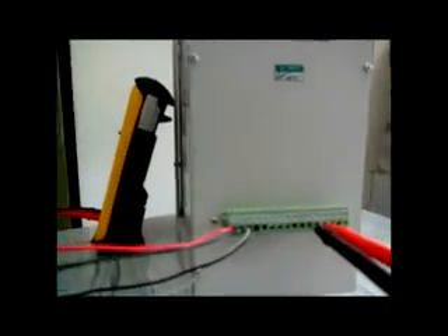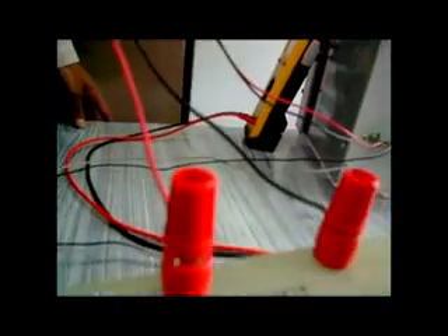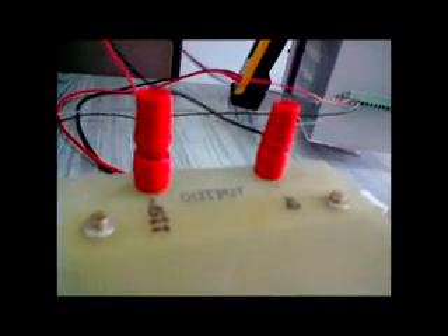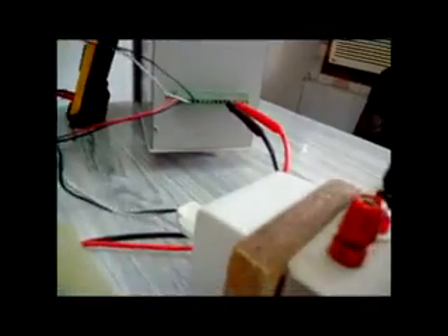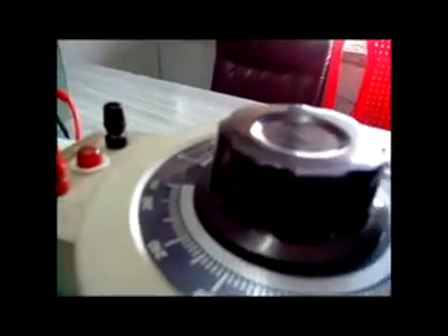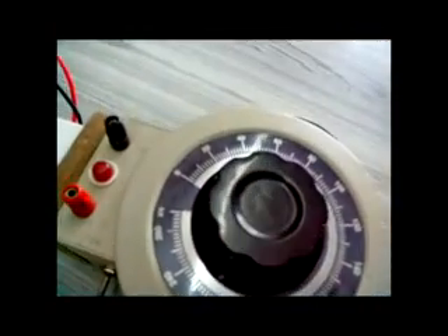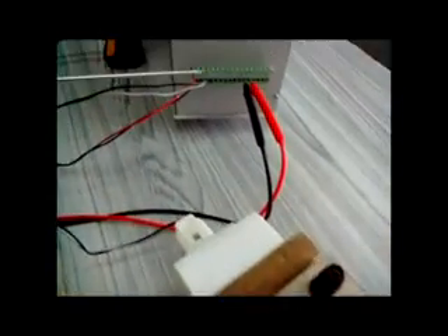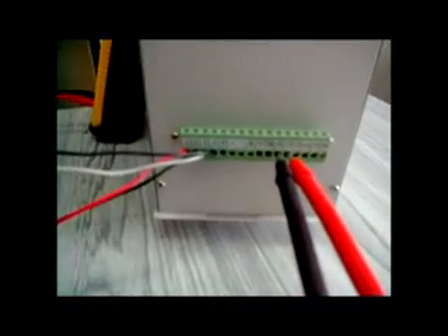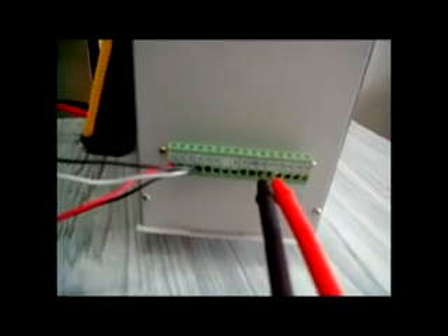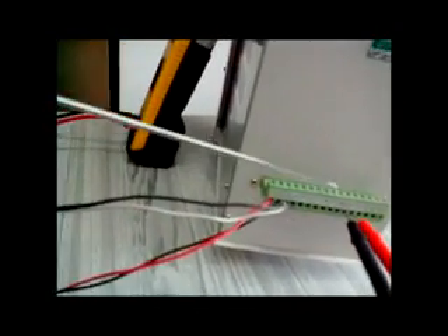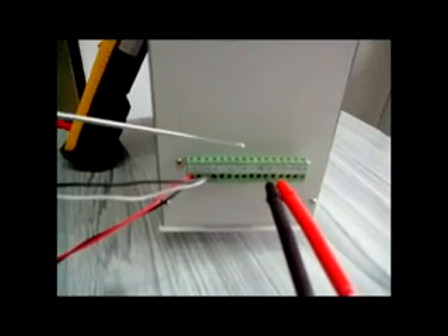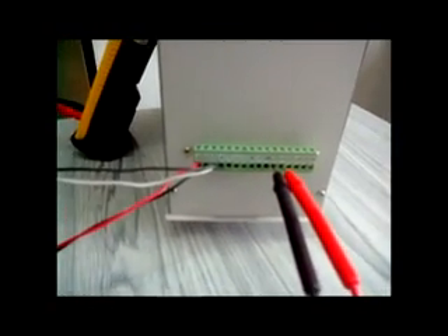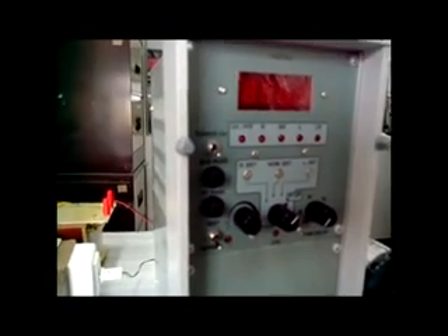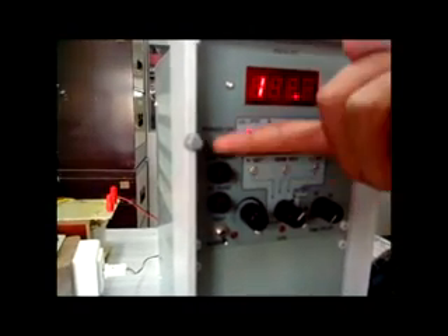We have provided 110 volt supply to terminals 1 and 2. Because this is a 110 volt auxiliary supply relay, we connect the PT terminals 3 and 4 to a variac or dimmerstat. Through this, we can regulate the PT voltage for operation check on the regulating relay. Here, pin numbers 13 and 14, the regulating relay output pulse, are connected with a continuity tester. When we get a regulating relay pulse, we observe continuity indication. Now we switch on the unit. We can see the voltage display.